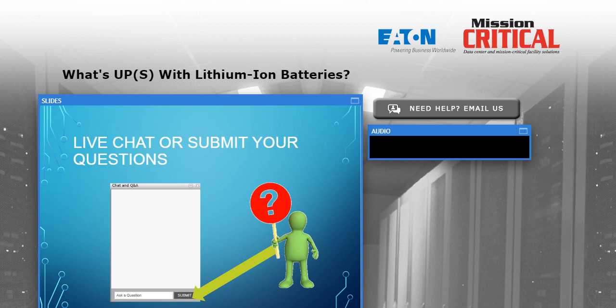But if you do find yourself deploying a lithium battery that is more than 70 kilowatt hours, then you may well be subject to that spacing requirement, and that would obliterate any of the space savings that you would otherwise have. What is the proper design to vent the flammable gases out of a room? Fortunately, we're able to use the similar ventilation that we would for a typical human-occupied space until the total quantity of lithium in the room exceeds 600 kilowatt hours.